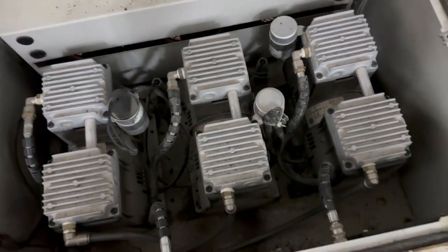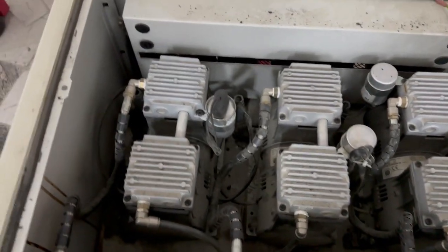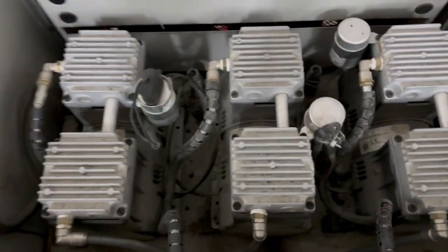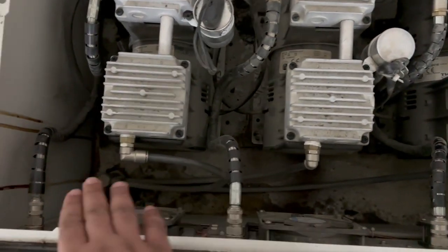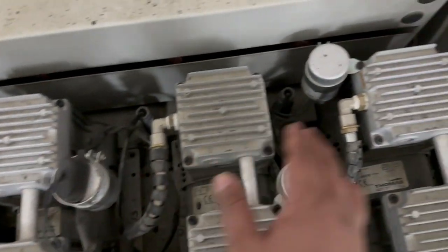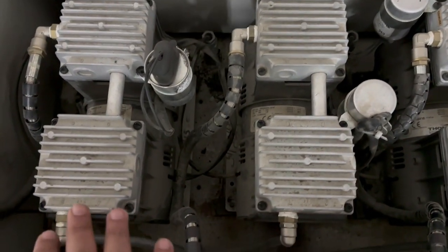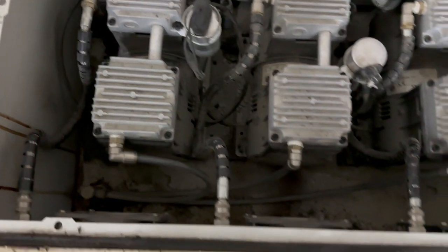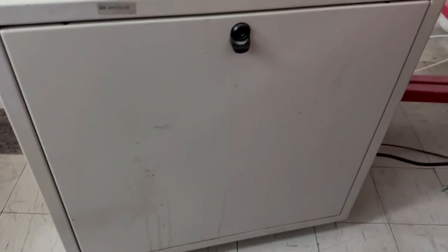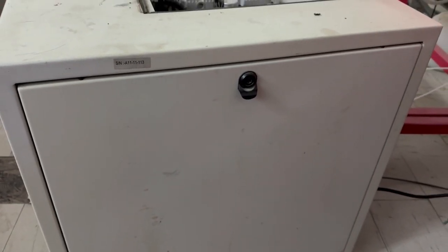We will troubleshoot this. So here we have 3 compressors which compress the air, and then output 1, output 2, output 3. Okay, so suction port 1, 2, 3. So 3 diaphragm pumps used as a compressor, and it compresses the air here, and then it goes in this way. So first we have to open this, and then I show you how it works.